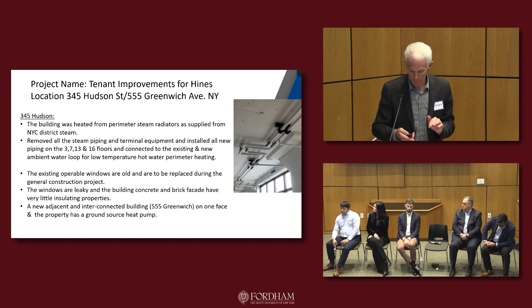Specifically at 345 Hudson, the building was heated from steam radiators supplied by the New York City District Steam. Basically, we removed all the steam piping and the terminal equipment and installed new piping on just the 4 floors, 3, 7, 13, and 16. Those are the tenanted floors, and connected to a new ambient water loop for low temperature hot water, and I'll speak to what low temperature is in a second. The existing operable windows on the facade of this building are leaky and old, and with the brick facade and so forth, there's going to be considerable losses through some of those, but there will be some replacement of those in the future. It's next to 555 Greenwich, which is a new building, and I think Jeff will speak to that in regards to it having a geothermal field and so forth, but it's interconnected to 345 Hudson.